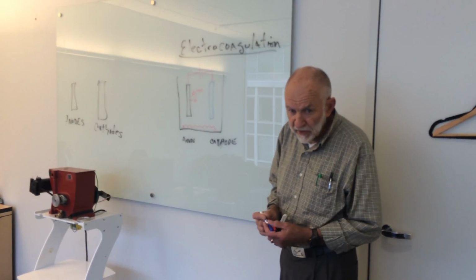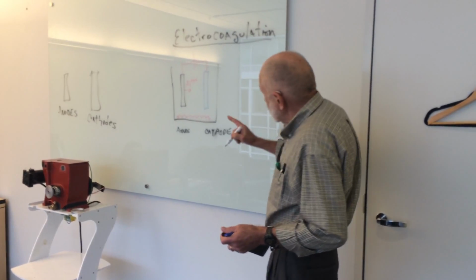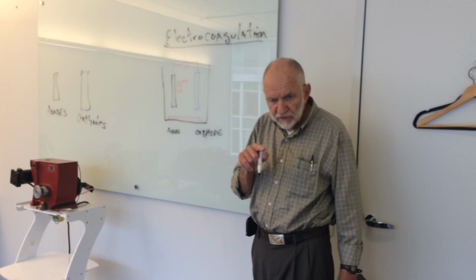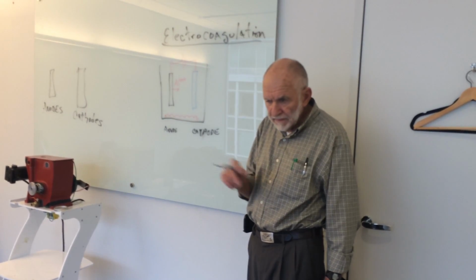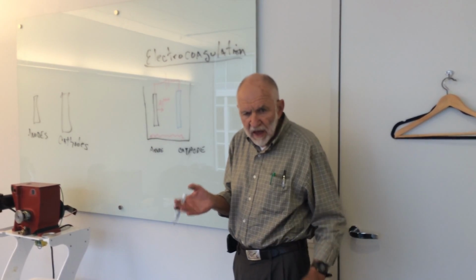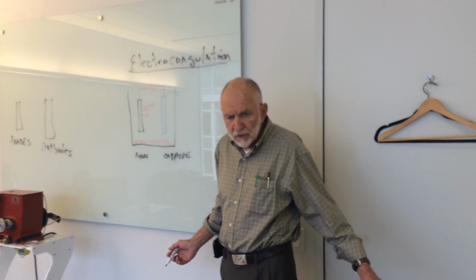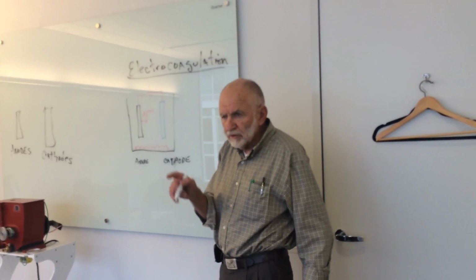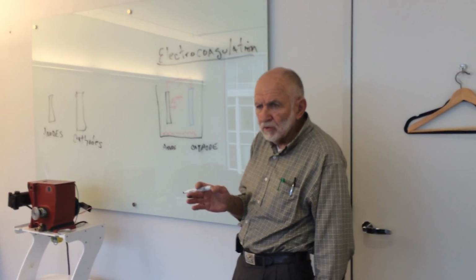Ocean water will be clean, but it won't be desalinated. It'll still have salt, so you can't drink it. You'd have to go through a desalination process, which is typically reverse osmosis or capacitive deionization. Both of those have a membrane associated with them, and if you don't clean all this junk out of the water ahead of time, you will destroy your membranes. So this is a pre-process for anybody that wants to do desalinization by reverse osmosis, and it works really well for that.